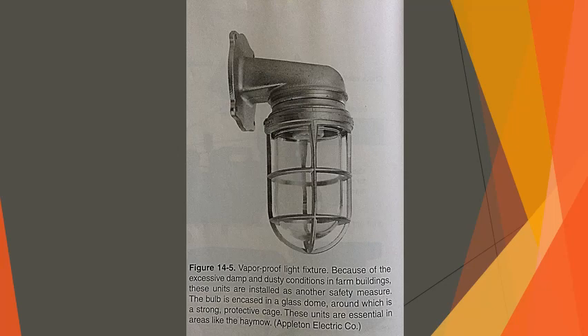Locating lights. Place lights at alley crossings, stairs, ladders, and chutes in the dairy farm. If ceilings are dark, use reflectors so light is directed downward rather than to the ceiling. Place the lights where joists, beams, and posts will not obstruct the light from a fixture. Place switches so that lighting can be controlled at all entrances to the building. Use three-way switches. As with residential wiring, pilot lights are advisable when switches control lights that cannot be seen from the switch location.